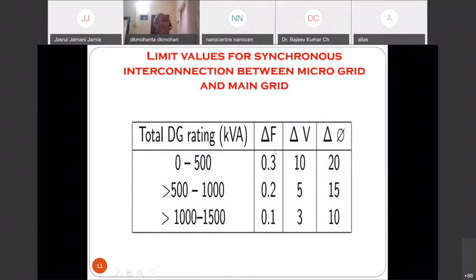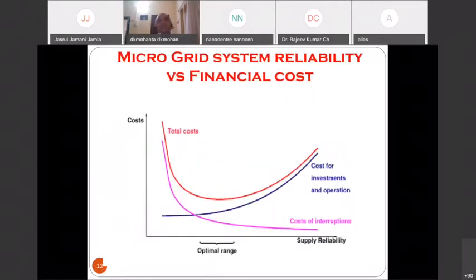So if it is from 0 to 500 kVA, the frequency deviation allowed is 0.3, and delta V is 10 volts, and this is the angle in degrees. So if you see here, as we go more and more in capacity of the DER, the allowed deviations will be less.